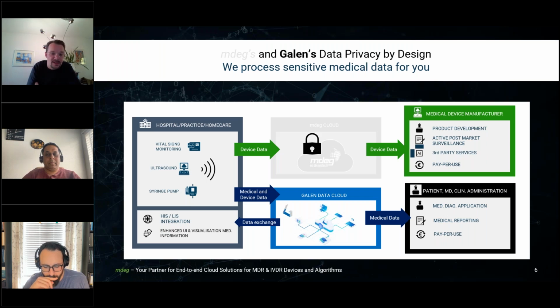If you have, just as an example, 100 devices out in one clinic, and you collect all the messages from those devices, and you see that the error message quantity is very low, then you can say in your post-market report, we have a number of error messages. We checked every individual message, all fine so far. This is for the medical device. If you go to the diagnostic devices, then they have to have a performance evaluation over their installed base. And usually we see also that the quantification of the diagnosis over all devices is helping for the performance evaluation.